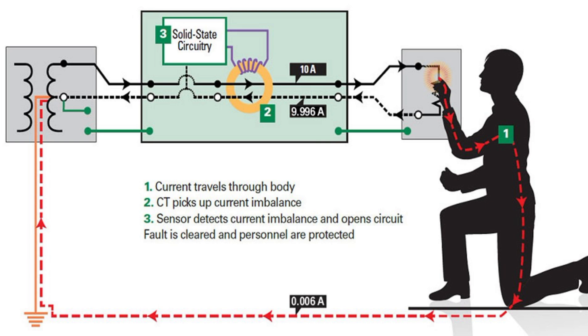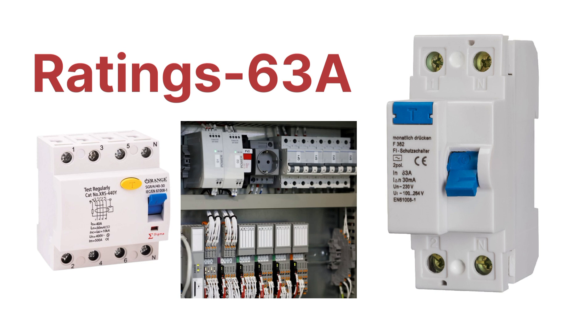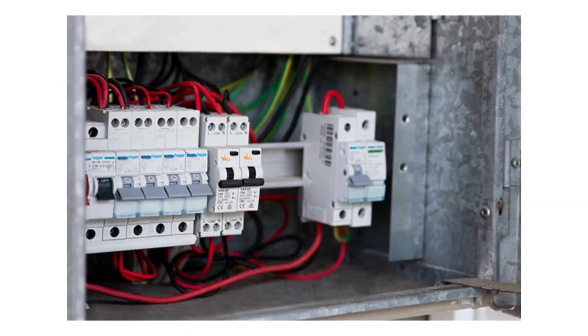This happens only when the circuit breaker detects changes in the incoming live wire and the outgoing neutral wire current. The RCCB trips to protect people and equipment from electric shocks and even possible fires. One thing to remember: RCCB has a rating of up to 63 amperes.